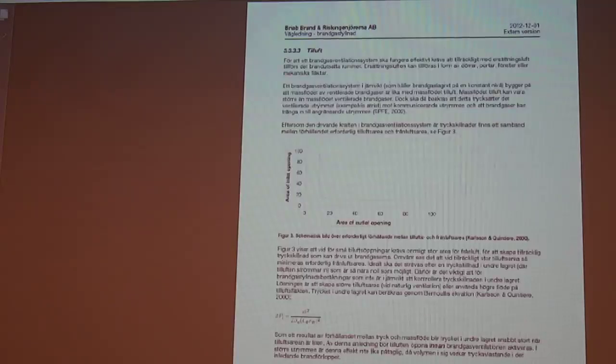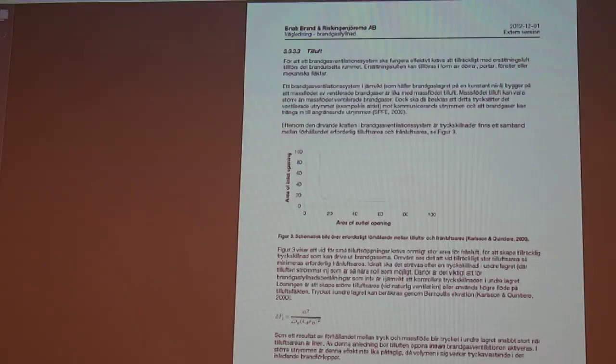And one important thing that we also have to highlight is, if you're gonna use smoke evacuation, you're gonna take something out from the building, you have to put something into the building. When we do this fire smoke simulation, we usually forget to ensure that we get the air into the building, and how the relation should be, so you have this in mind when you start modeling. If it's a two-zone model or if it's a CFD model, you always have to ensure an inlet.